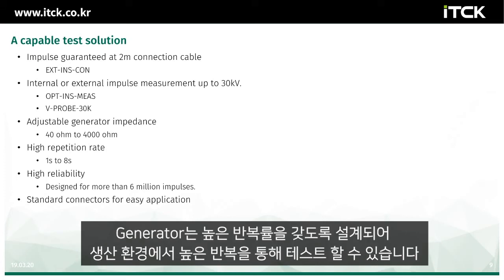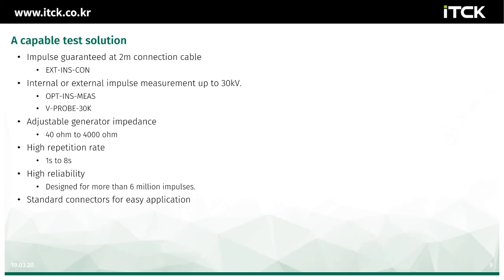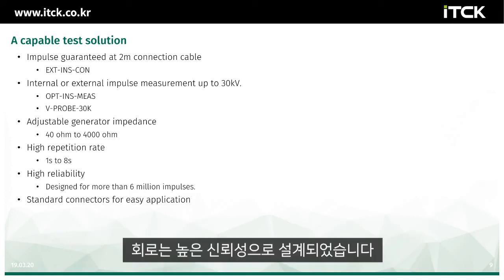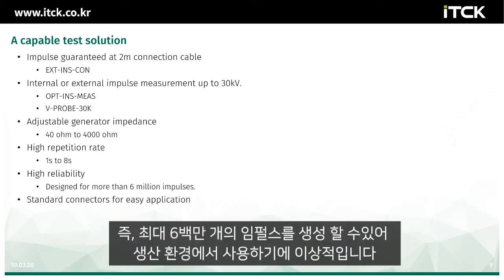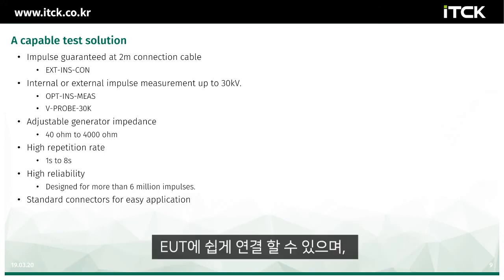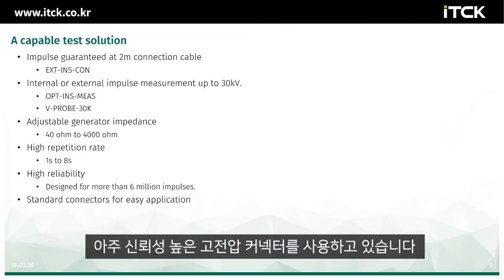The generators are designed to have a high repetition rate, enabling testing to a high repetition in the production environment. The circuits are designed with high reliability. That means that we can generate up to 6 million impulses, making the instrument ideal for use in a production environment. The high voltage connectors are standard, they're readily available, making it easy to connect to the EUTs.